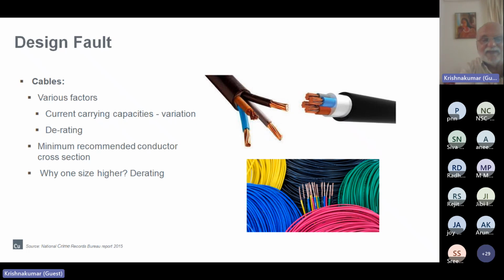So two things have happened comparing decades-back installations with now: the possibility of a short circuit has gone up, and at the same time the magnitude of short circuit current has gone up multifold. So, alongside load factor, this is to be considered as a significant factor.